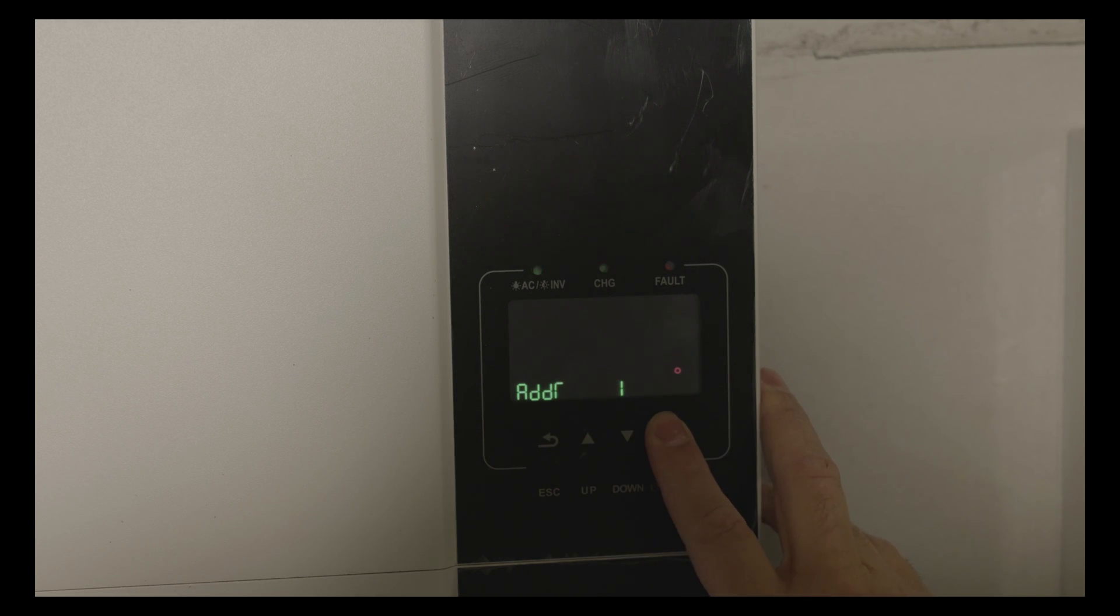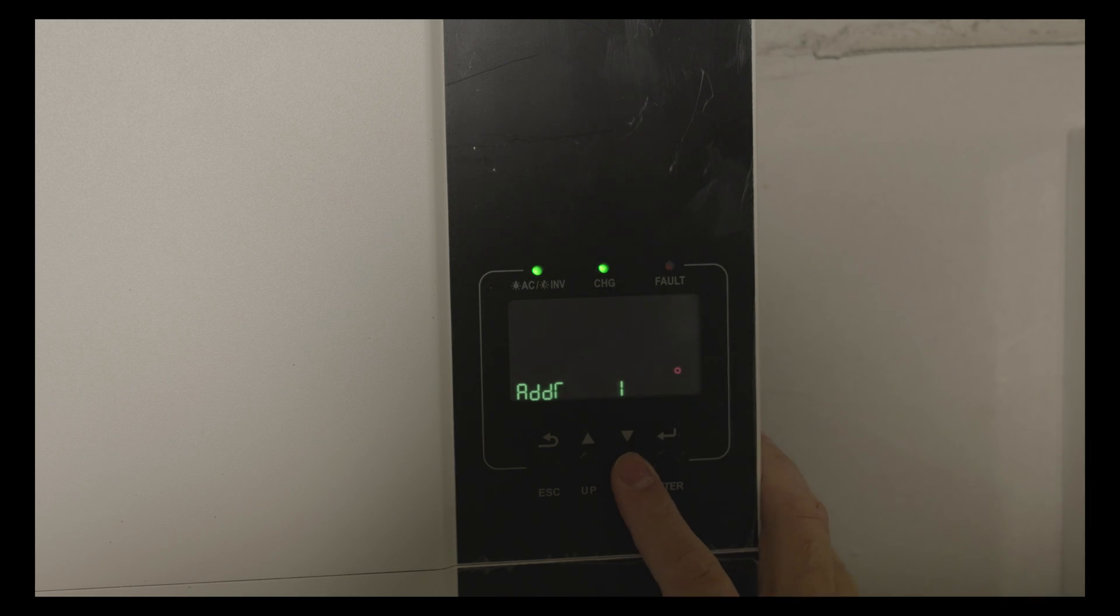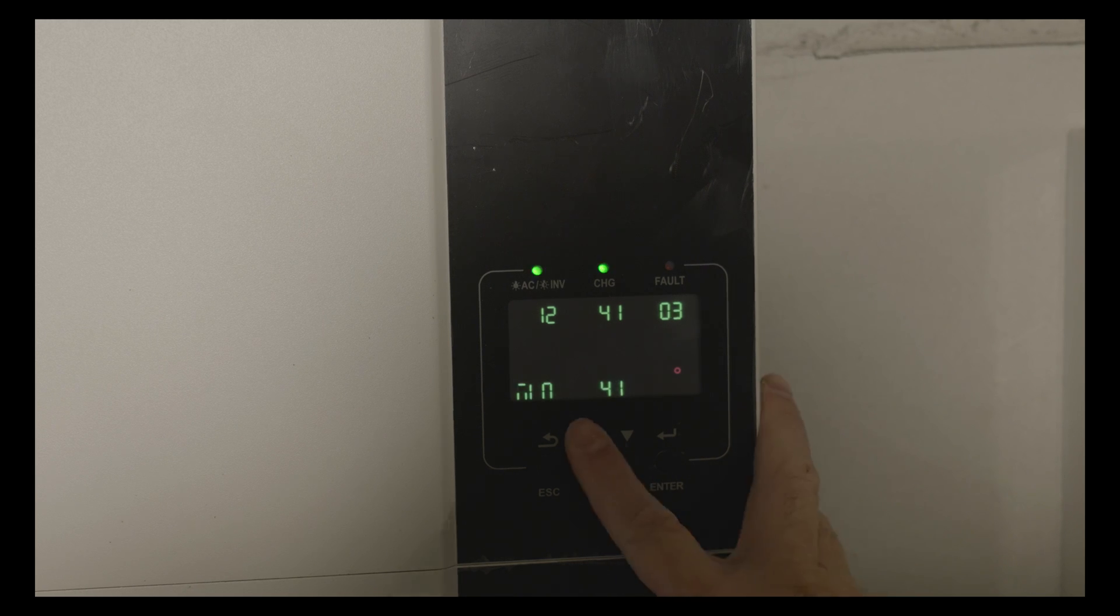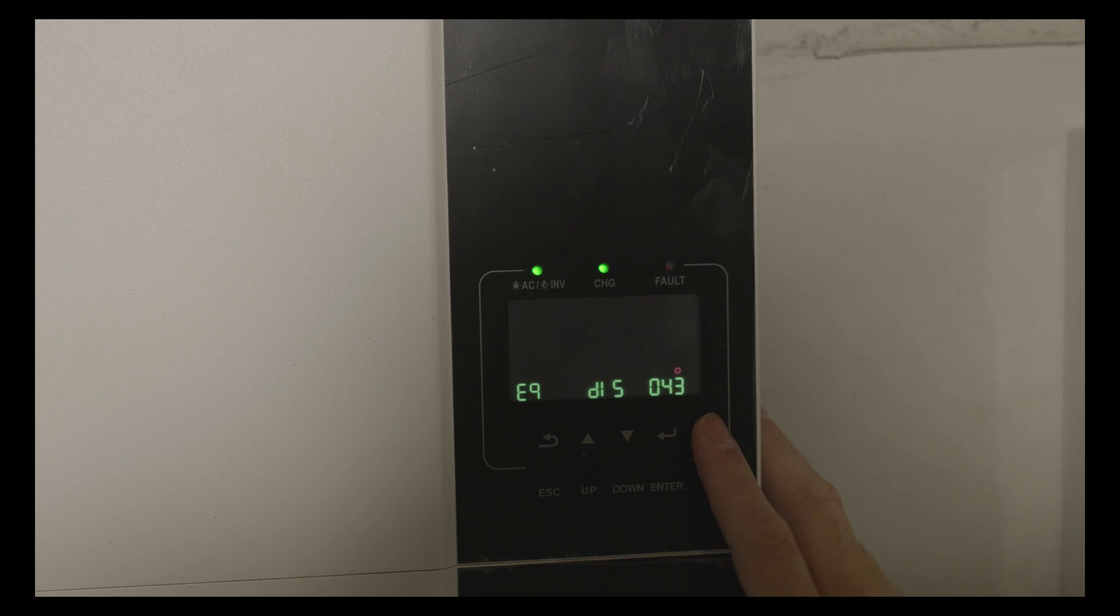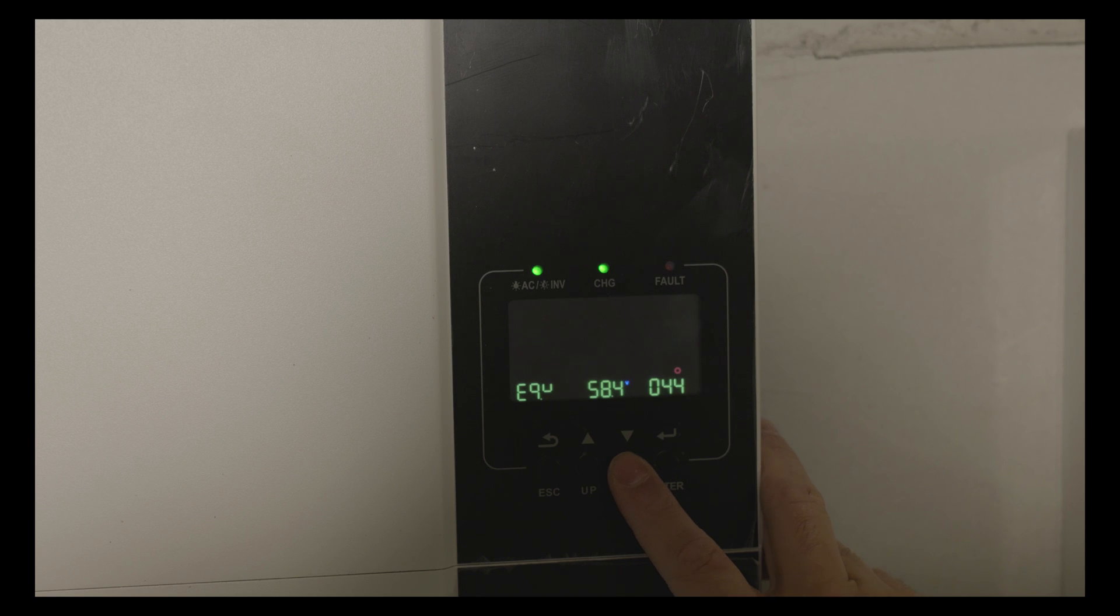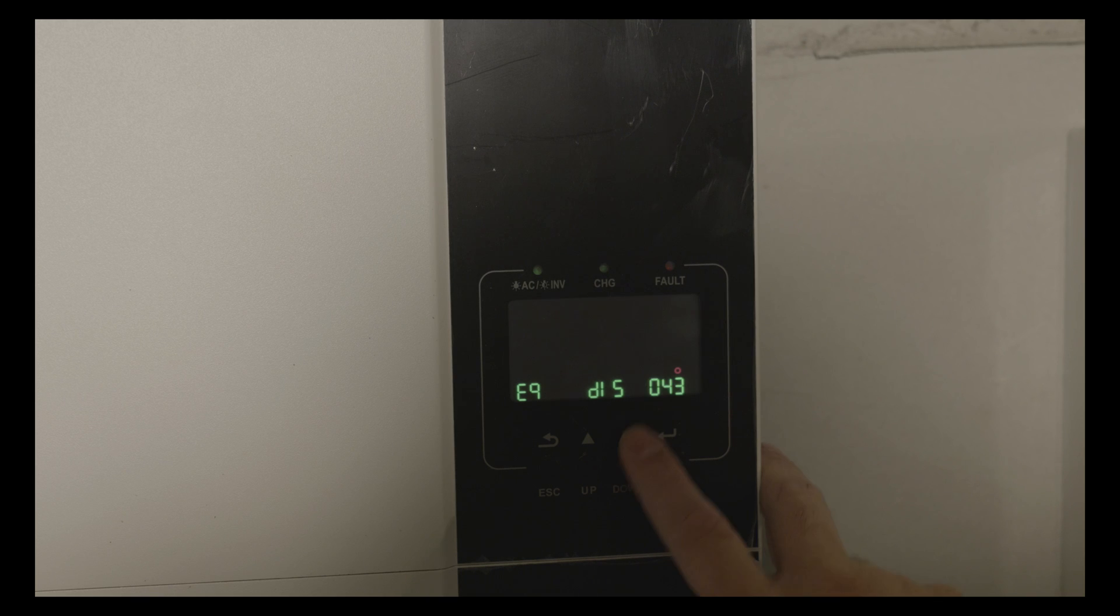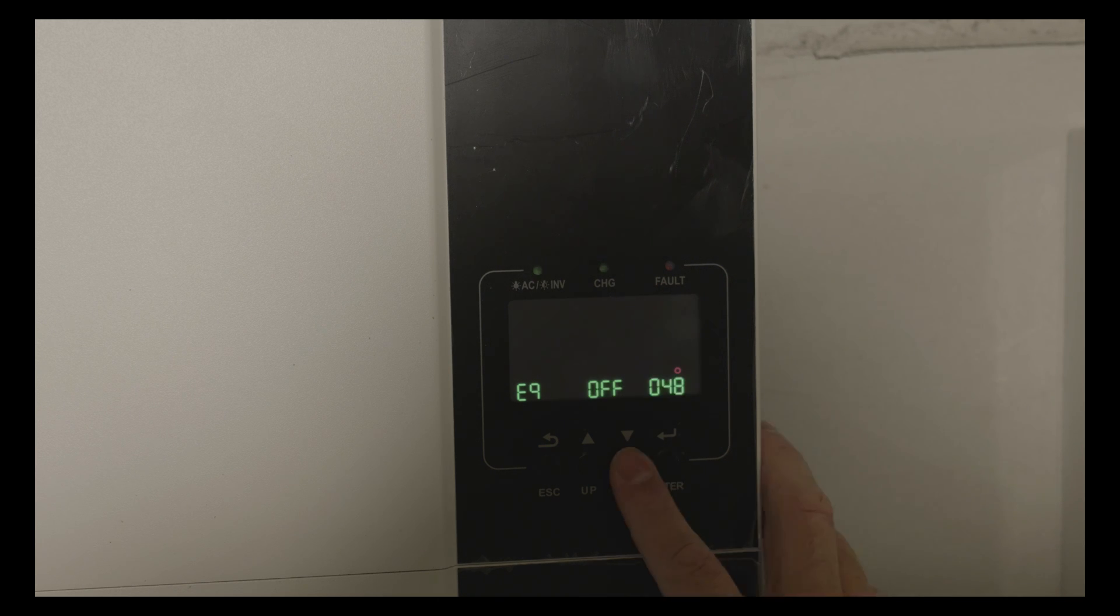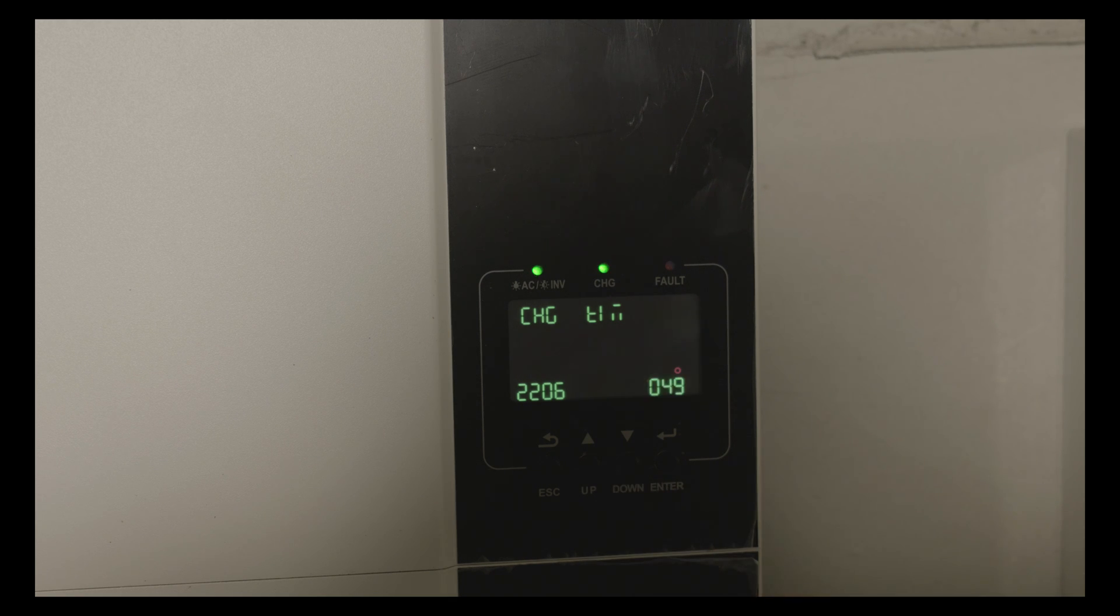Option 28 I haven't changed, this is the default setting, and then we have year, month, date, hour, minute, second. The battery equalization settings from 43 to 48, we are not using them because we are using lithium batteries and I don't think they need equalization.